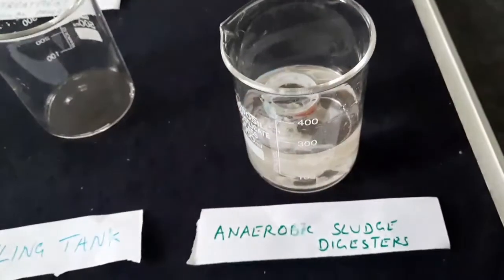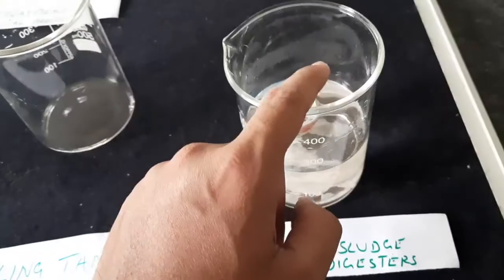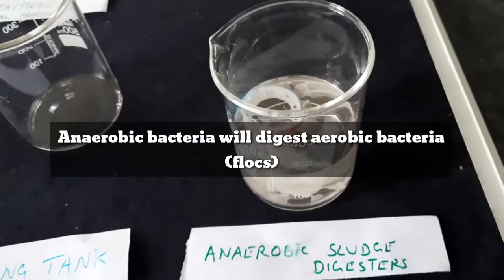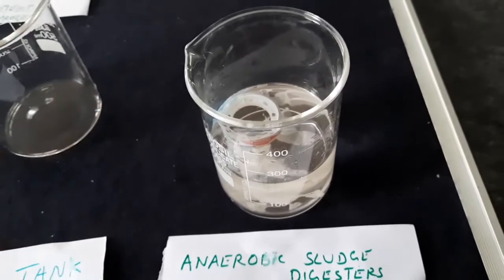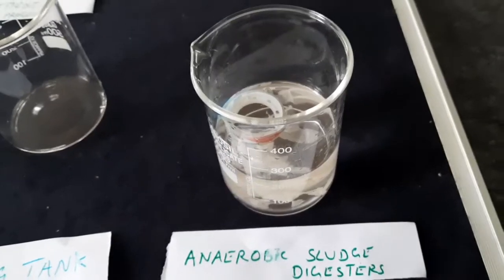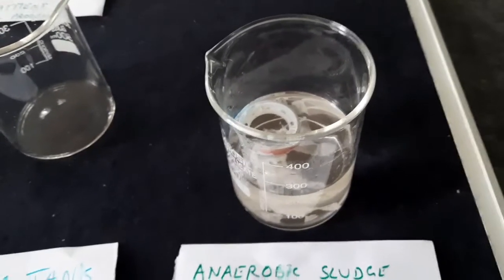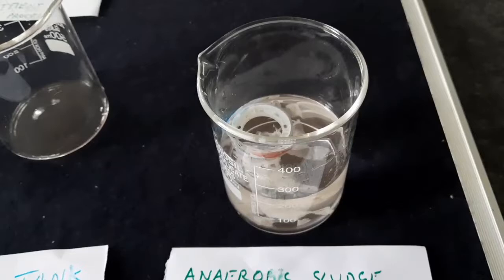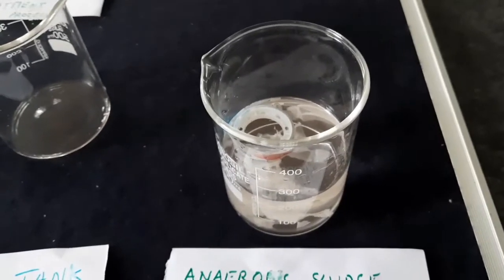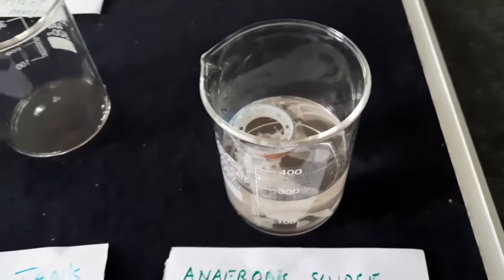See, the anaerobic sludge digester mainly contains anaerobic bacteria which are going to digest the aerobic bacteria, that is, our activated sludge. It will be completely digested. They will kill the aerobic bacteria. During the process, they will release H2S, carbon dioxide and methane gases, which could be used as biogas, that is, as a source of energy.